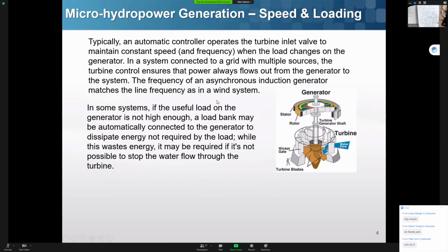And so in here they said if your load changes, they might have a load bank with automatic control connected to the generator to dissipate energy. So that's considered a dump load. And in the code book, we can see what is said. Because if you don't have those controllers or governors to regulate the rotating speed of this generator, you will just basically use some dump load to dissipate the actual energy.